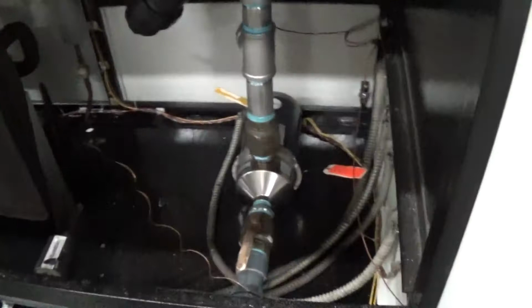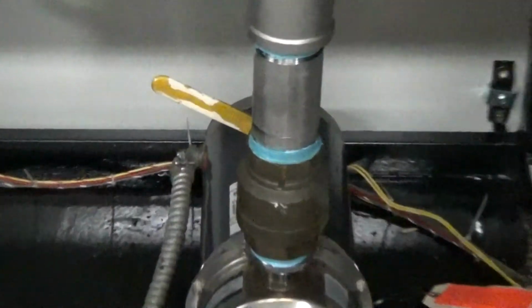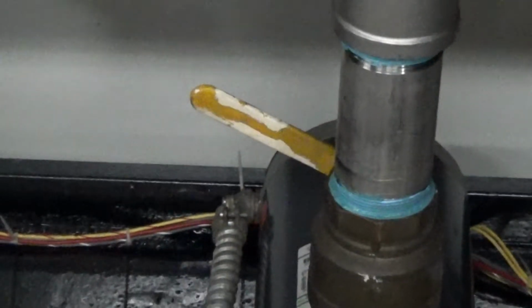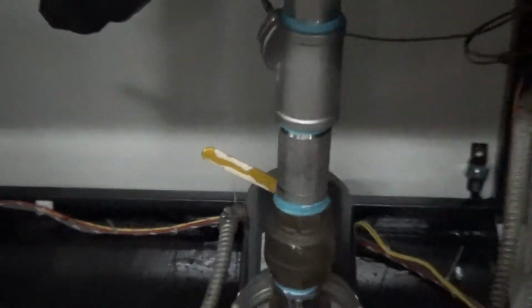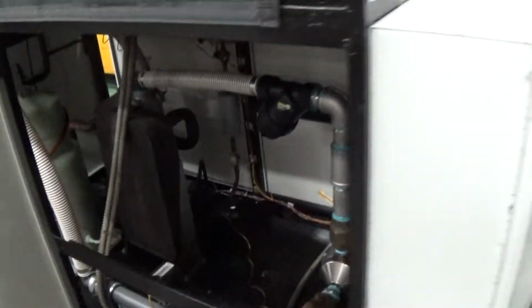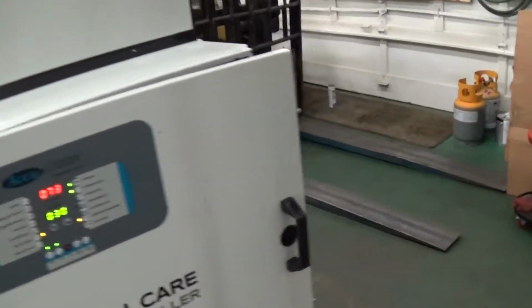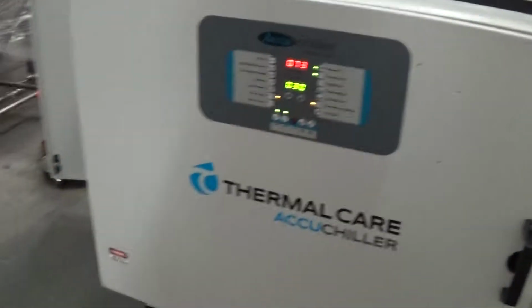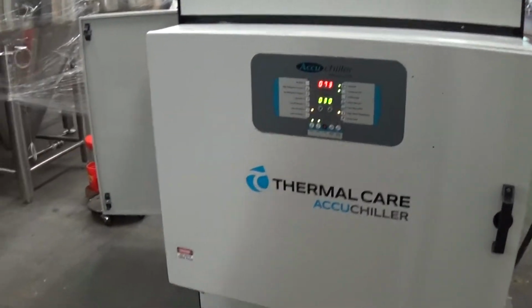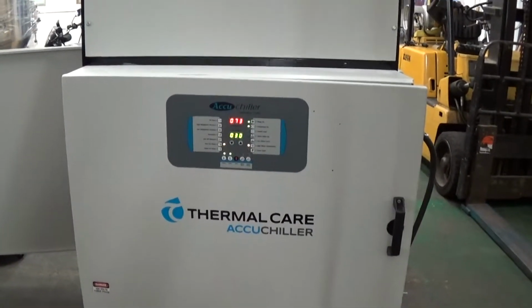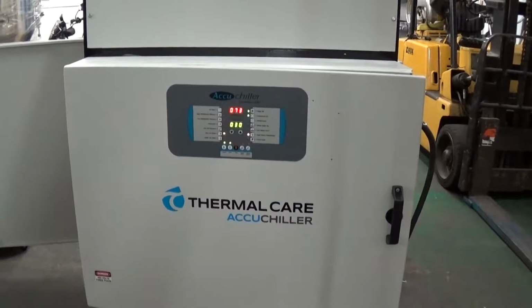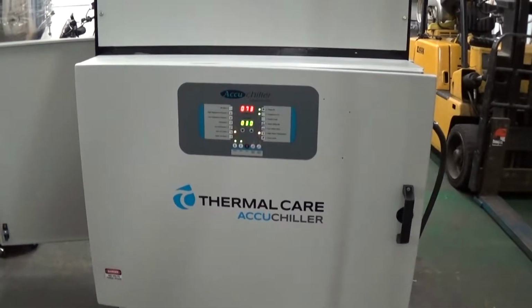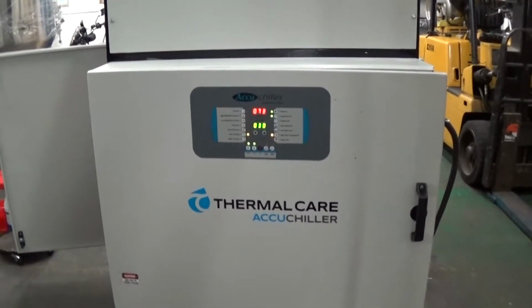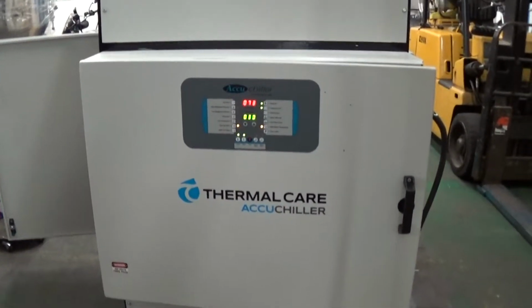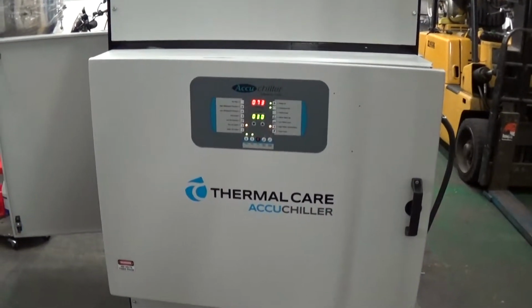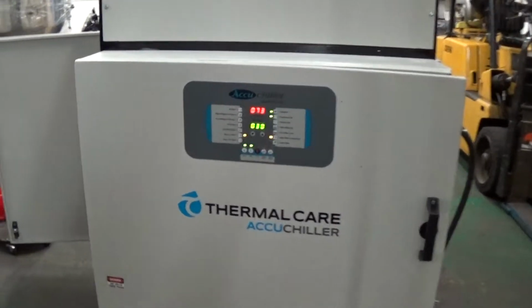Again, on our pump here, on the discharge side, we have that about 50% closed. If you have a shut-off right at the inlet into the tank that you're cooling, it is sometimes nicer to have that restriction for the pump, to bring the pump within the amp zone farther away than there. So at any rate, you have to have the pump have enough back pressure so it falls into the nameplate amps that it's calling on the ID tag.